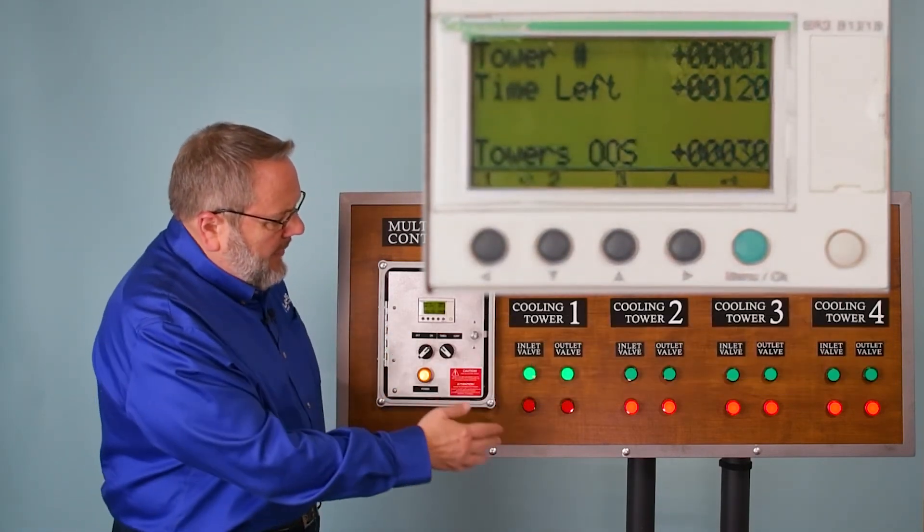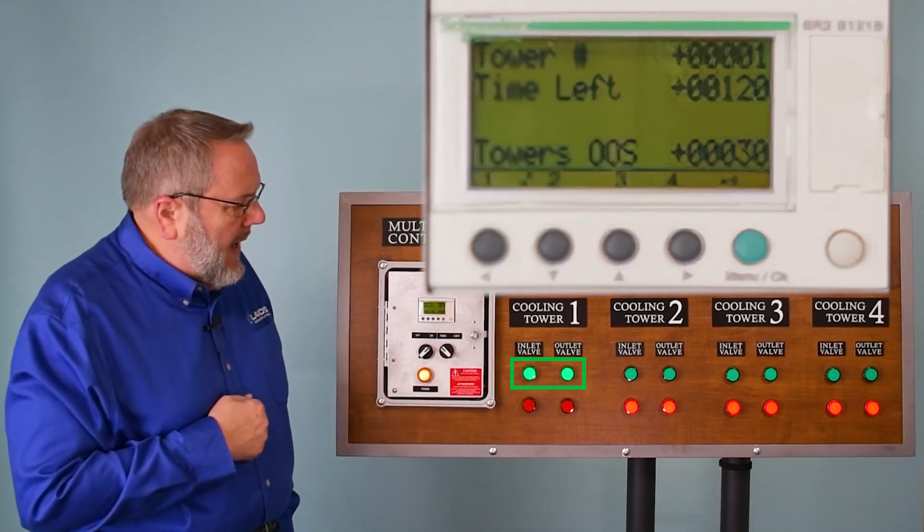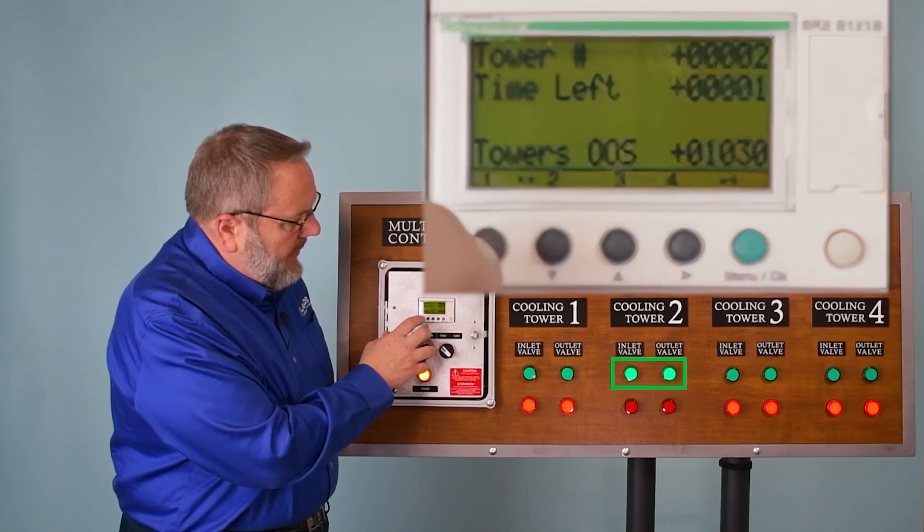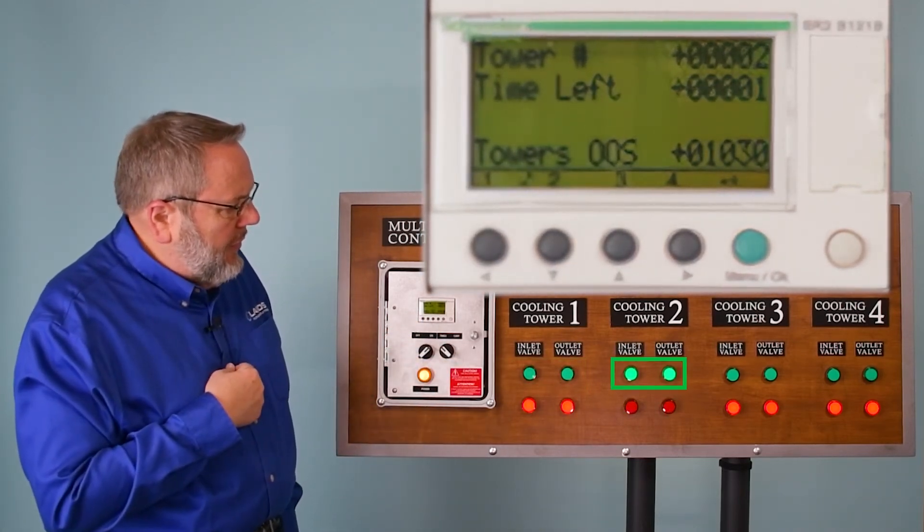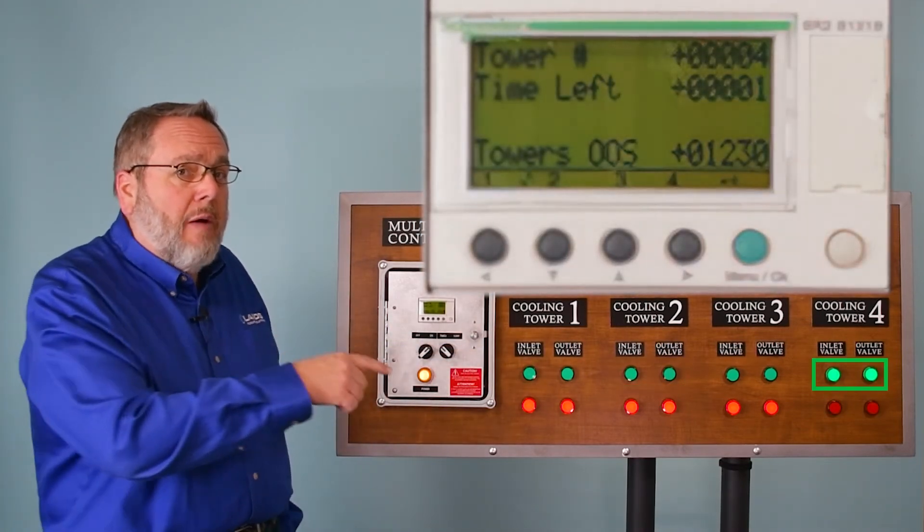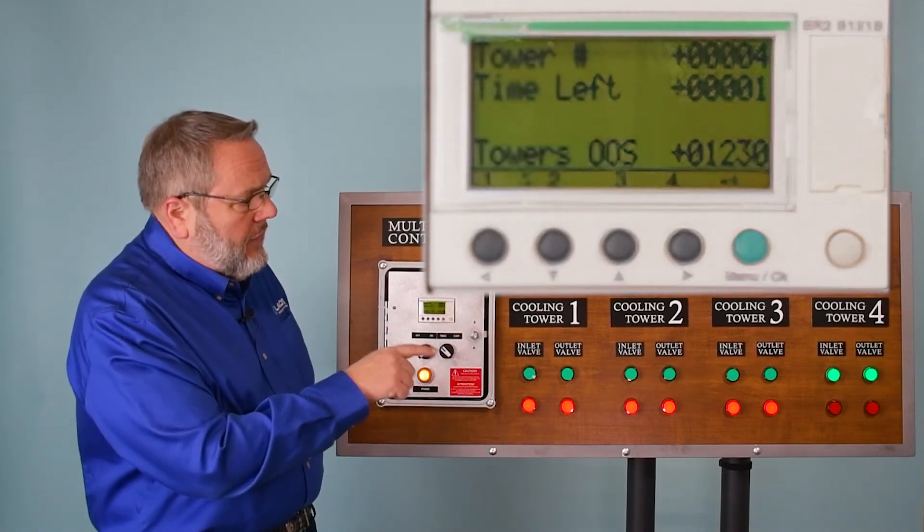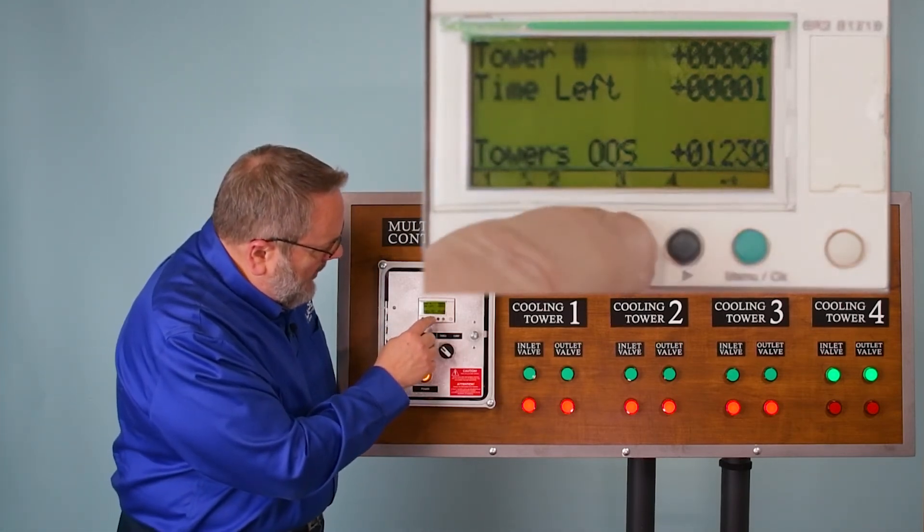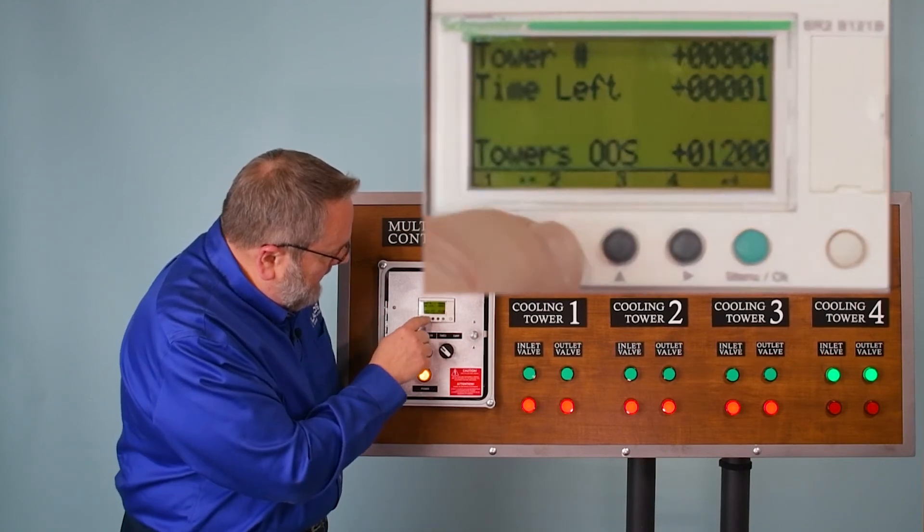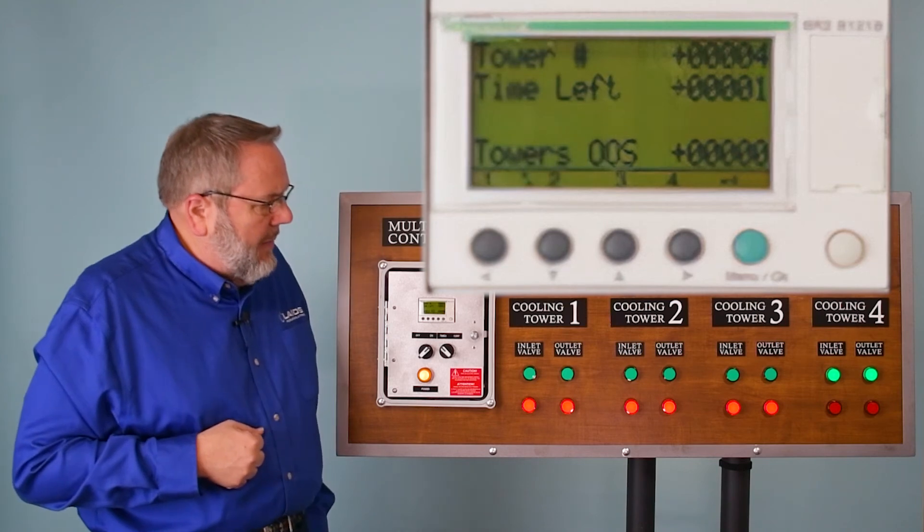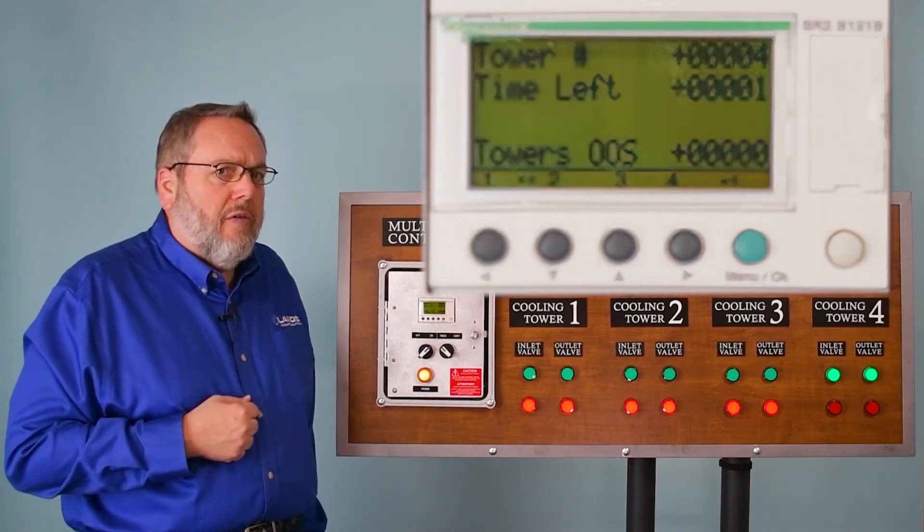So what you'll see here, if you look at the green lights, tower one is running right now. If I close off tower one, now tower two is running. Close off tower two, it bypassed three and went straight to four. So three is closed, it will not operate until you take it back off with the button like this. So again, when you see all zeros there, that means all towers are open, all towers are going to run.